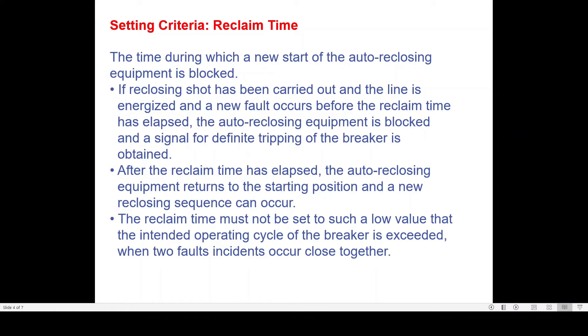Since your circuit breaker has operated once for opening and again for closing, the mechanism of the circuit breaker needs some time to regain healthiness. For a pneumatic breaker, air pressure development using a compressor takes some time. Similarly, for spring charging of a spring circuit breaker, the motor requires some amount of time. Within that time, if there is a fault, you cannot operate your circuit breaker again for a trip-close cycle, as it might affect circuit breaker performance and there are chances of failure. This time required for healthiness of the circuit breaker mechanism is called reclaim time, and during this time autoreclosure is blocked.